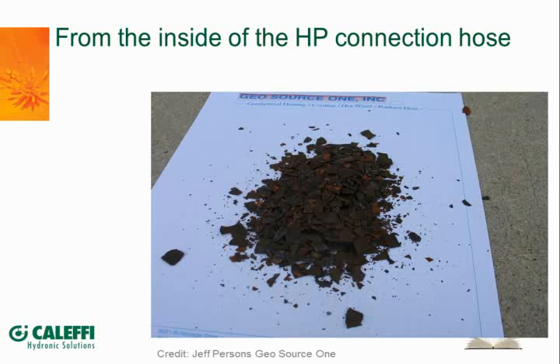This slide shows a pile of brown debris, which is actually redeposited ferrous material from a black iron piping system. It was redeposited inside the rubber flexible hoses connecting the geothermal machines to the building piping. When I was replacing the machine, I thought these hoses were fatigued with age because they felt hard and crunchy, so we cut them out to replace them. Lo and behold, the hard, crunchy material inside the hose was redeposited ferrous metal from the system, not fatigue in the hose itself. The hose was perfect after being cleaned out, but flexing it gave that crunchy feeling from the material coming out.